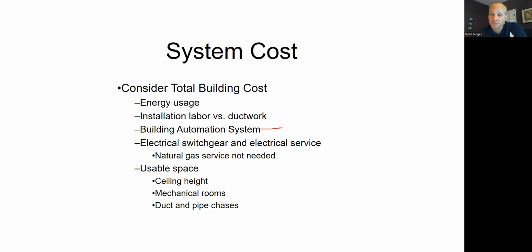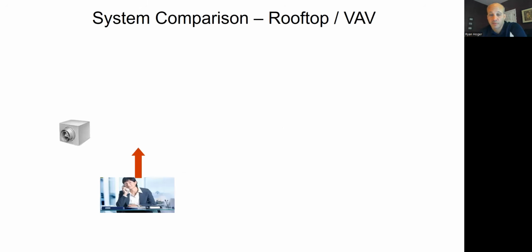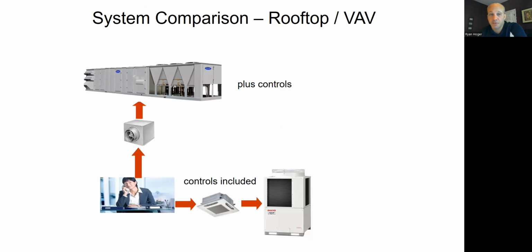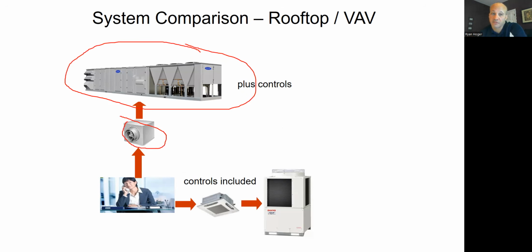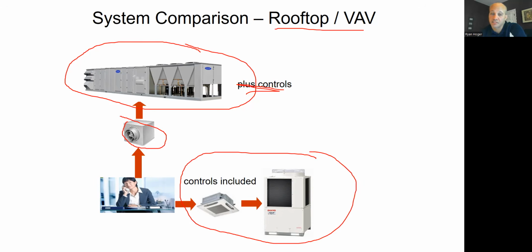How much space I have, mechanical rooms, things like that. If I'm looking at a VAV rooftop application, I'm buying a VAV rooftop unit, right, which has multiple compressors, variable speed fan, and all that. And each zone gets some kind of VAV box or fan power box, and I have to add my controls. And I need to add all of that up, and then I compare it to VRF, which already has the controls included.